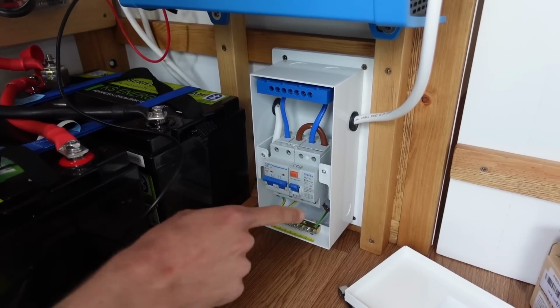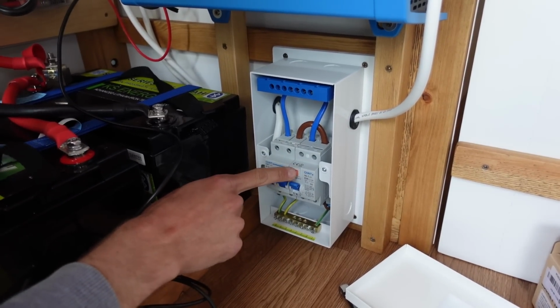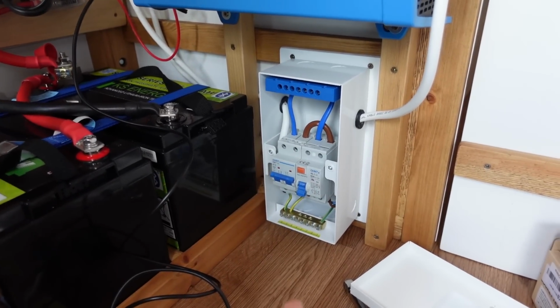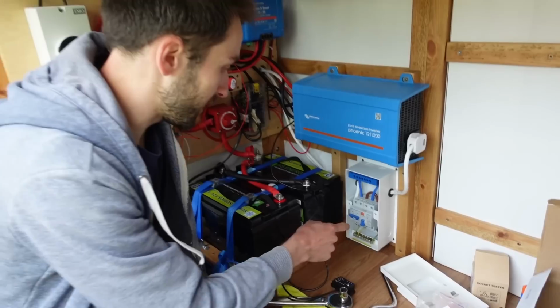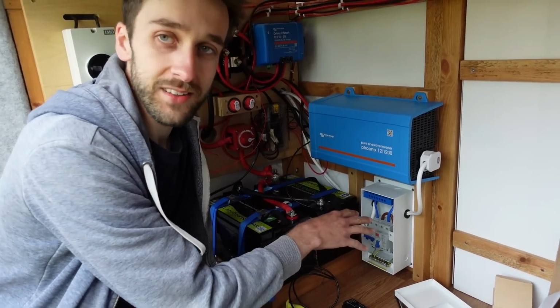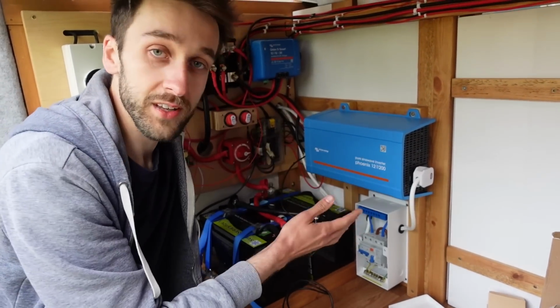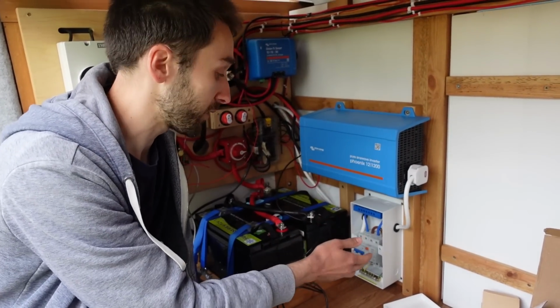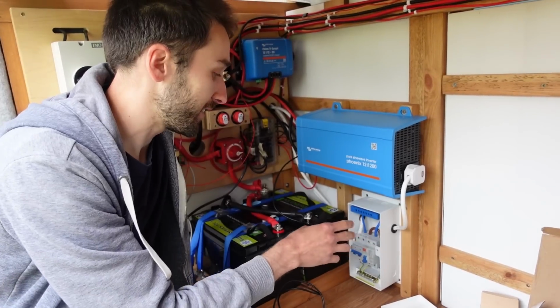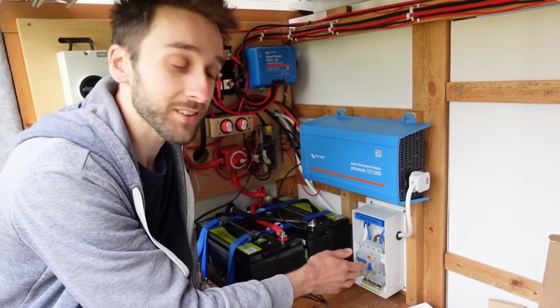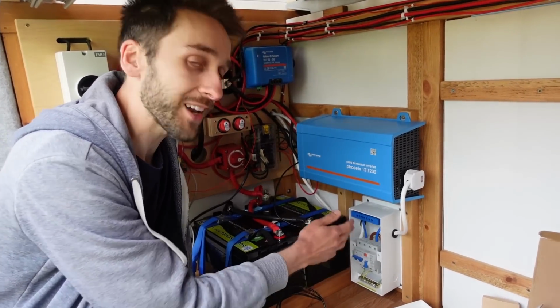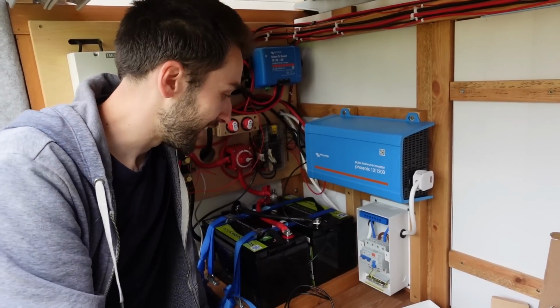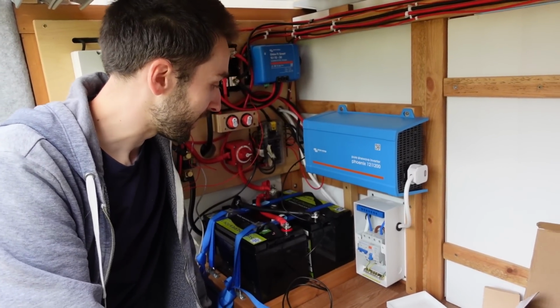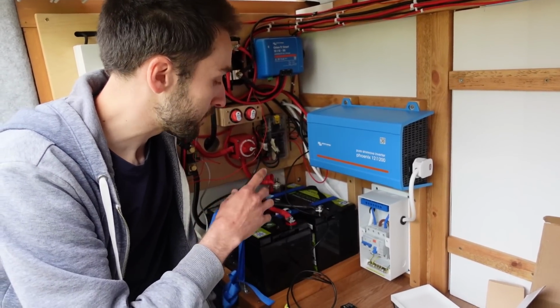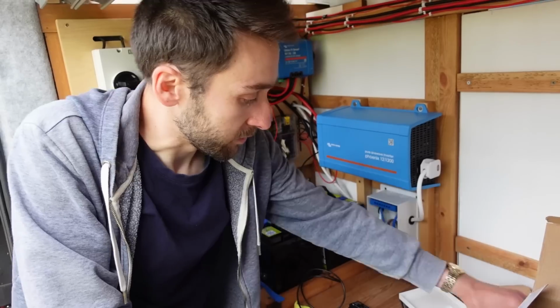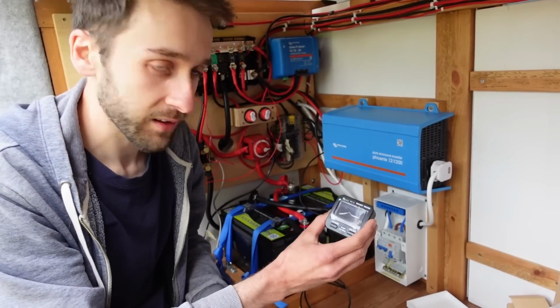The RCDs have this test button on there, so if I press that, then you can see it trips. But what's interesting about RCDs is that test button doesn't really test the whole circuit and doesn't prove that the RCD is working. What that does is just test that it electrically and mechanically works. So it tests that it can work, but not that it will work. So what we actually need to do is to plug something into a socket and then check that it actually trips. What we've got is this socket tester.